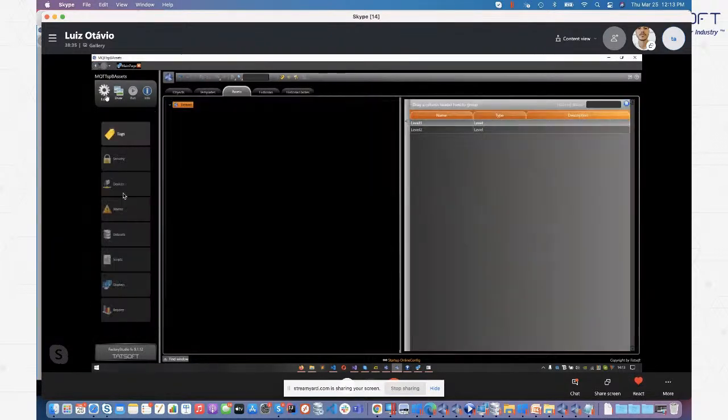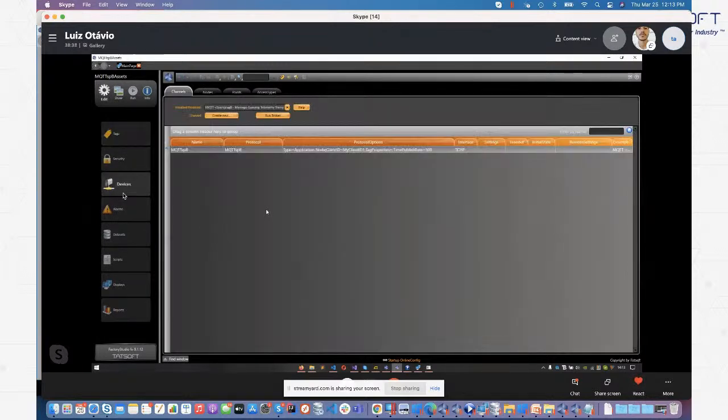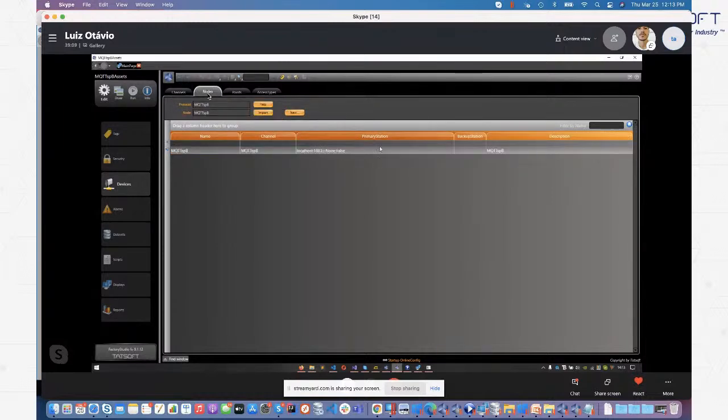On device channels, we added the support for MQTT. And what Walter was pointing out, we are using MQTT as example now, but we have that same ability with Canary Labs, and we are adding OPC UA, Rockwell, Factory Studio, PI. We can have many systems acting as tag providers with auto-discovery. And then in nodes, we are mapping to the specific IP and port details of that broker, okay?